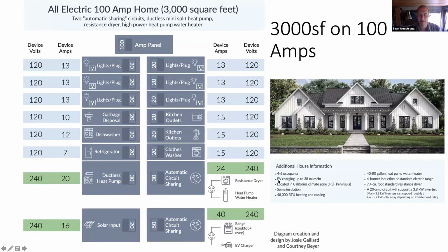Now, how this works out: this is a 3,000 square foot house running on a 100 amp panel. That's a smaller panel—they started installing those in the 60s. Nowadays people usually have a 200 amp panel. But if you don't want to or can't upsize the panel or service, this is what your panel would look like, with all the normal stuff here in blue.